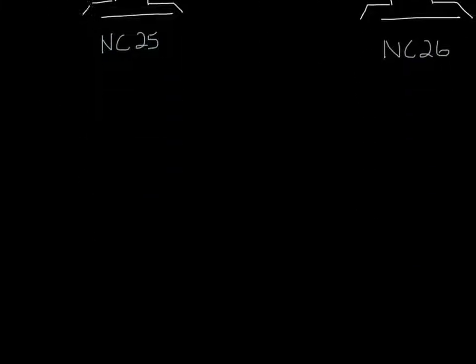Okay, let's scoot this up and out of the way for now. The next best option would be a soft radius of flex duct, kind of like this. This will add about 3 NC to our diffuser data, so now it'll be an NC28 installation.